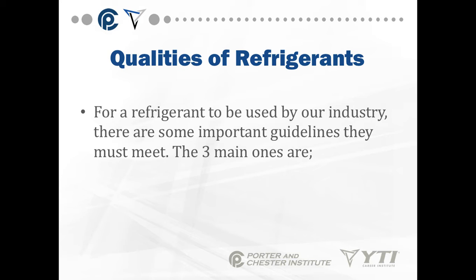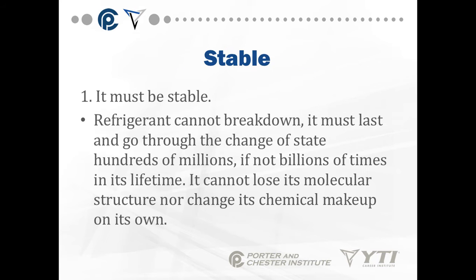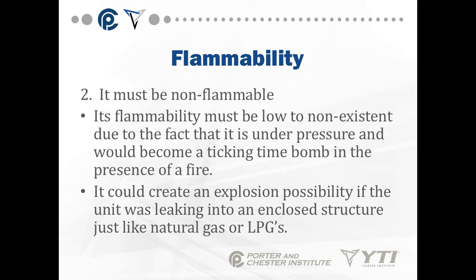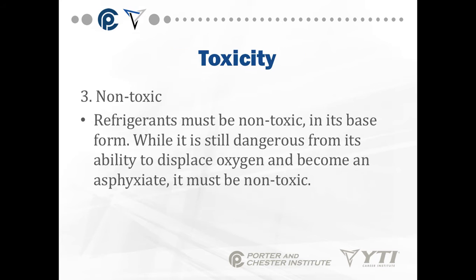We're going to be talking about refrigerants throughout this course. For a refrigerant to be used by our industry, there are some important guidelines. It must be stable — refrigerant cannot break down on its own; it has to go through the change of state billions of times without losing its molecular structure. It must not be flammable — flammability must be very low to non-existent, as it's under pressure and would become a serious explosion risk in the presence of fire or if leaking into an enclosed structure.